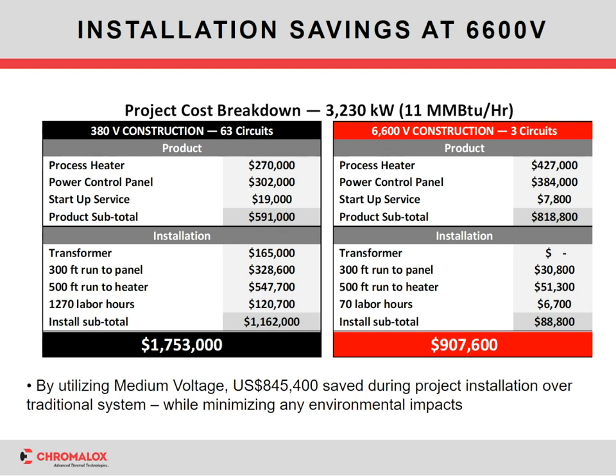Again, this was a little over a 3,000 kilowatt system. You can see where the medium voltage product was more expensive than a low voltage product. However, if you look at the next set of lines, that's where you can see a medium voltage system really lowers the overall cost of the customer. They're able to eliminate the total installation price of the transformer, the price of the transformer product, and also the cost of the wiring drops significantly, because if you remember that amperage we looked at before, it's almost 17 times less amperage they have to put in there, and that's 60 less circuits worth of labor and burden. So at an installation price, they were able to save over $800,000 while minimizing any environmental impacts.